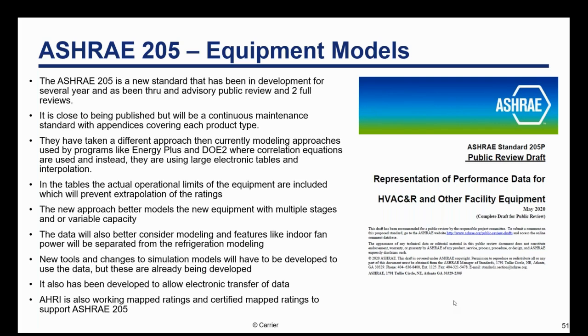One of the things we've learned is a lot of the modeling approaches that are used in EnergyPlus and tools like that were developed 20, 25 years ago. They really don't do a good job on intensive machines, variable speed machines. So this new approach will basically give a much better approach that then can be ported into these programs, backed up by certification programs. So there's a lot of work on this. This has been in a long development, but we're getting close to getting it released. Next slide.